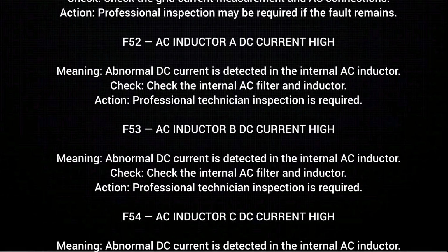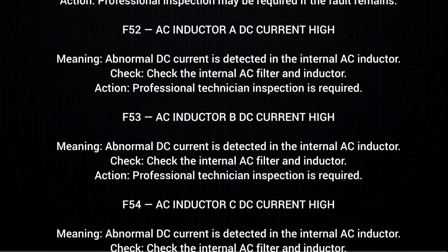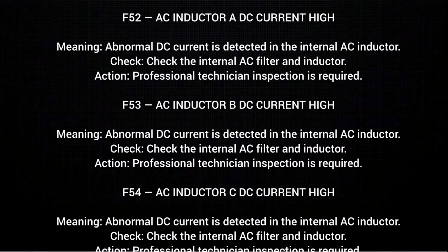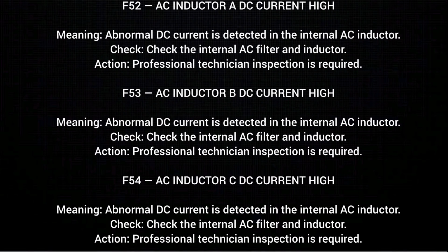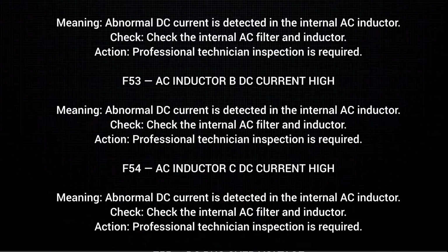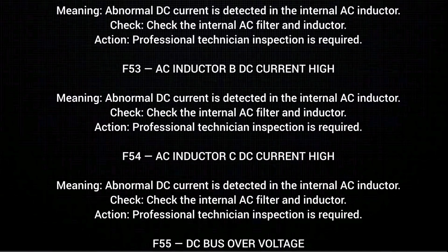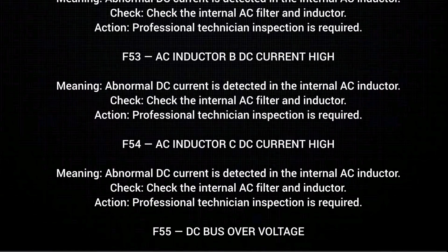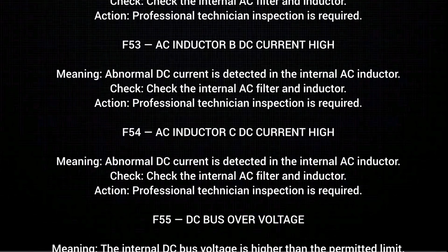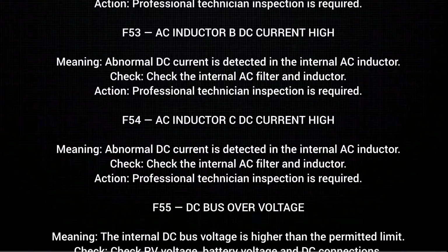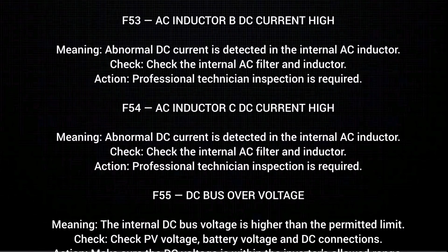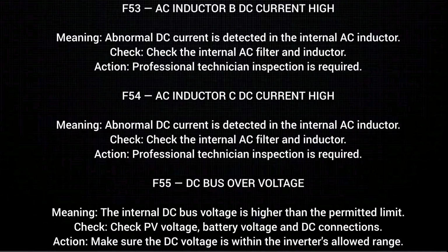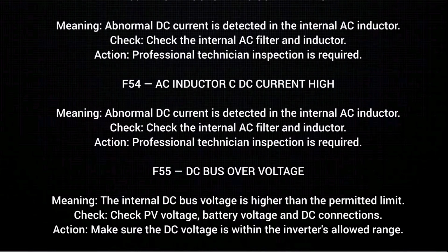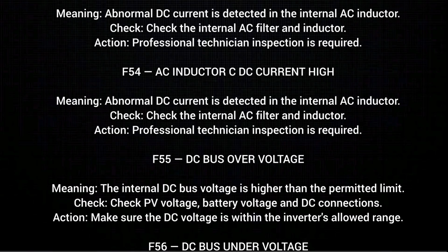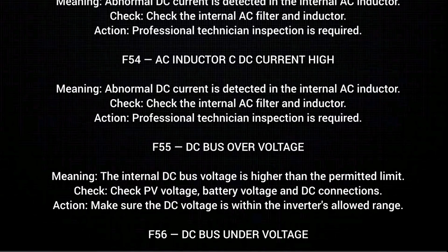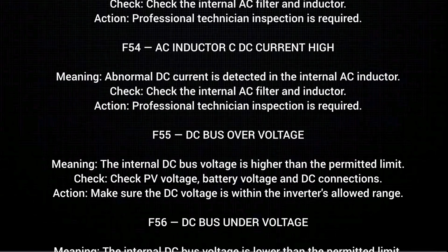F54. AC inductor C DC current high, meaning abnormal DC current is detected in the internal AC inductor. Check. Check the internal AC filter and inductor. Action. Professional technician inspection is required. F55. DC bus over voltage, meaning the internal DC bus voltage is higher than the permitted limit. Check. Check PV voltage, battery voltage and DC connections.